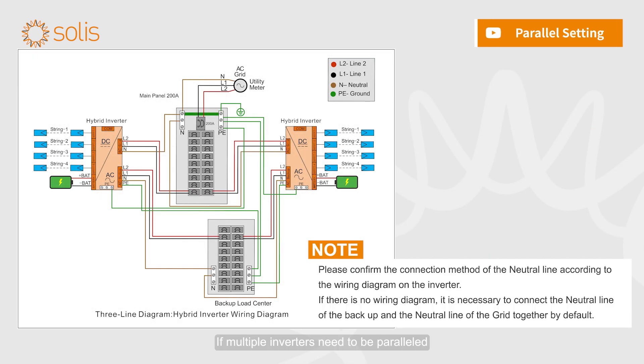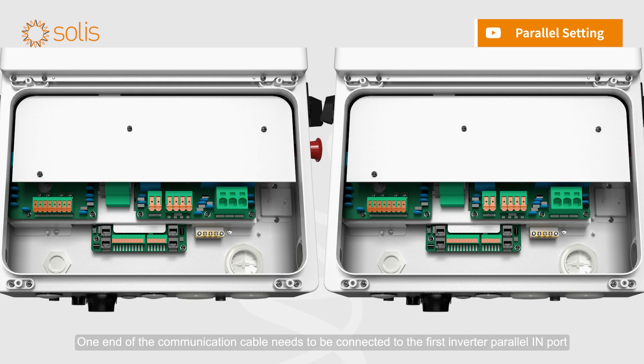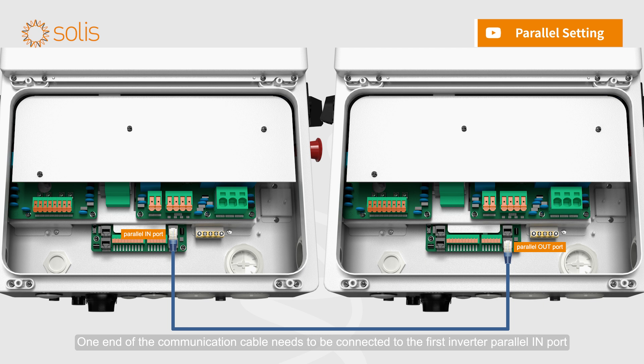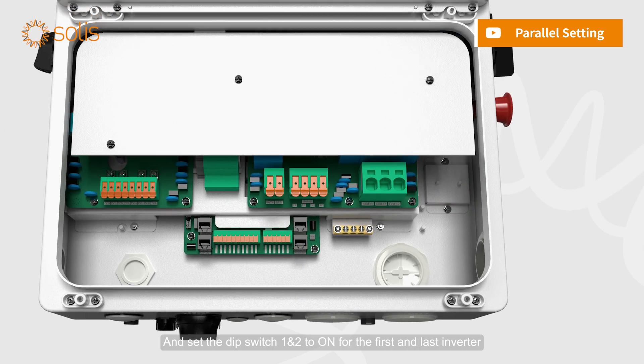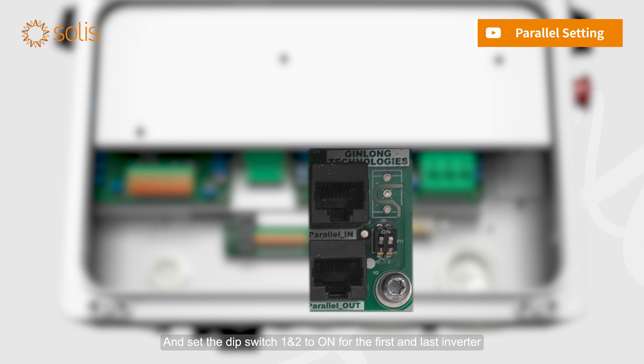If multiple inverters need to be paralleled, one end of the communication cable needs to be connected to the first inverter parallel in port and the other end to the second inverter parallel out port, and set DIP switch 1 and 2 to on for the first and last inverter.